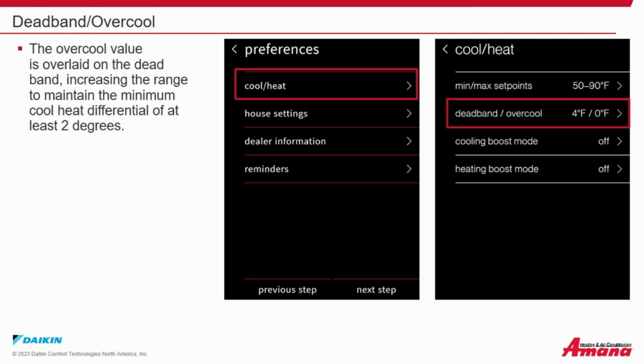Deadband overcool. The overcool value is overlaid on the deadband, increasing the range to maintain the minimum cool heat differential of at least 2 degrees.